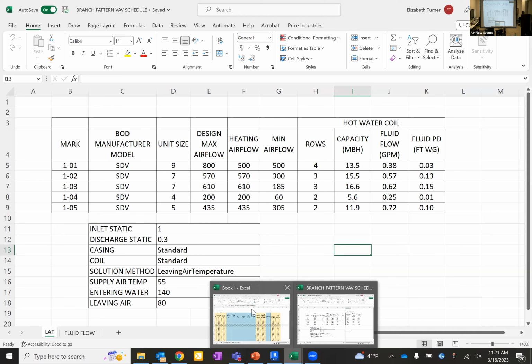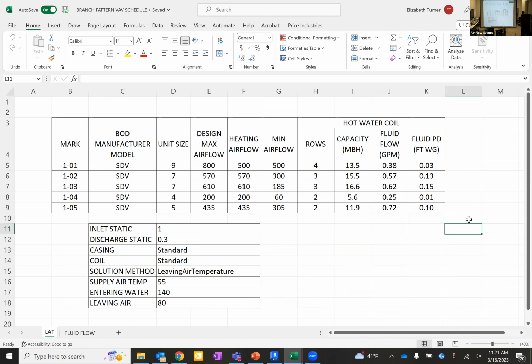Well, and the thing about this engineer's schedule, which, God, I hope they don't use 4 rows very regularly, but that happens. When you use your regular formula to calculate GPM and MBH, it doesn't match the catalog data. So, expand on that. The biggest benefit is that there are a large number of engineers who are not using manufacturer software. Up until now, we've been trying to preach, use manufacturer software, because if you are just using engineering heat transfer calculations, you're not going to get exactly what the catalog will show. So at least using somebody's software will get you closer than those equations.